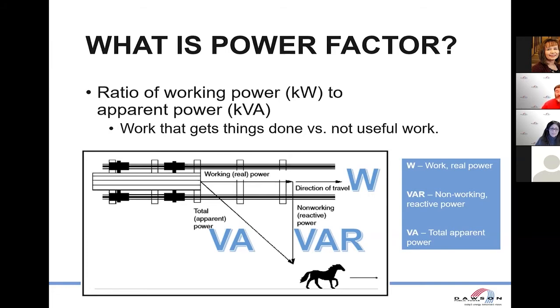Now there's non-working power also, reactive power, right? If you've ever stood to the side and tried to pull something, you know it's harder to pull it from the side than it is from straight ahead. So that non-working or reactive power, in the case of an electric motor, is VARs. Your total power, which is the combination of watts and VARs, and we can thank Mr. Pythagoras, who you probably haven't had to think about much since high school, for helping us calculate your total apparent power, which is volt amps.